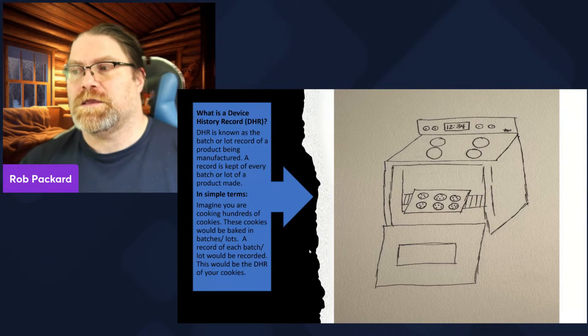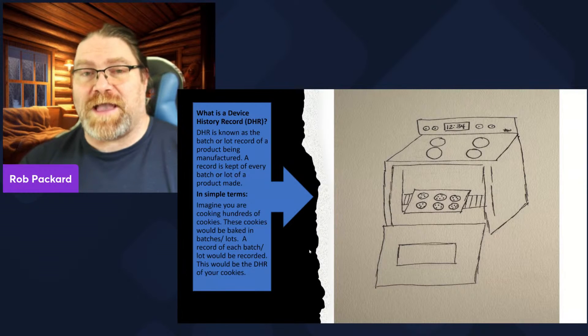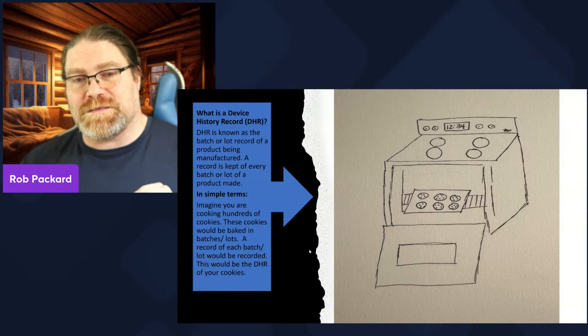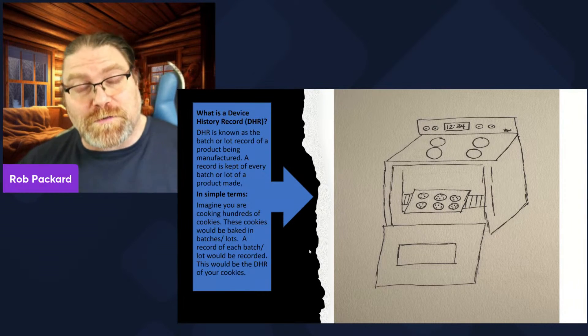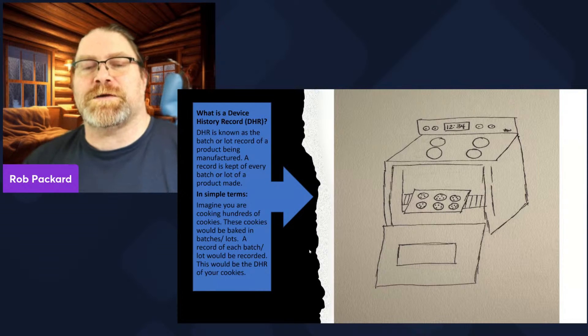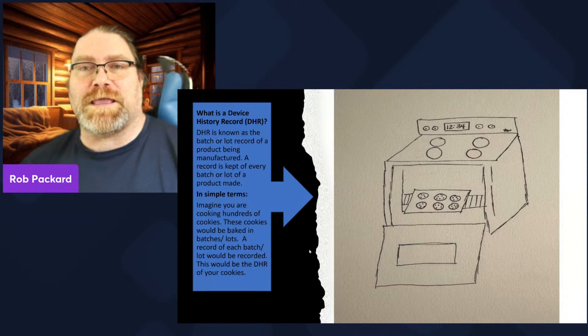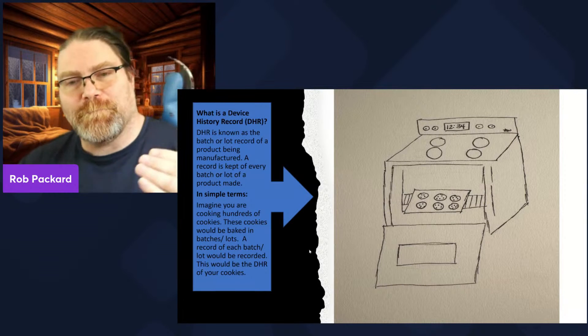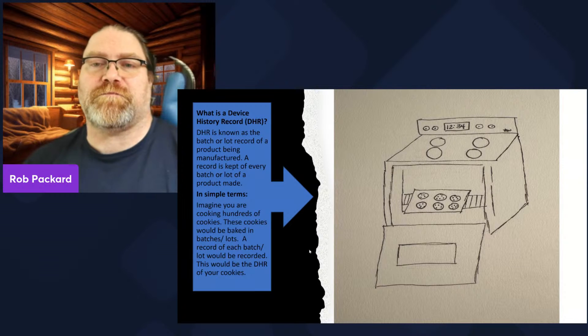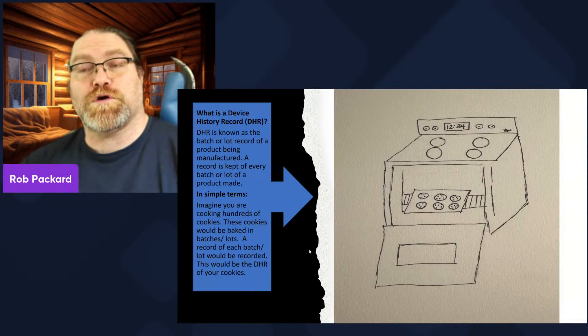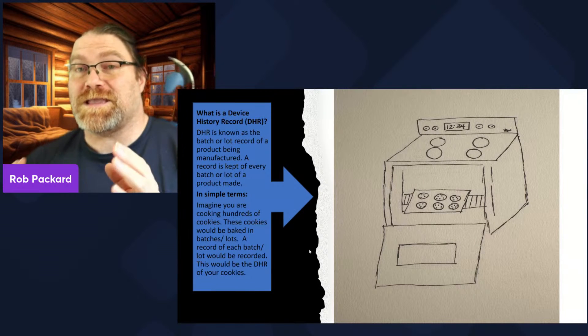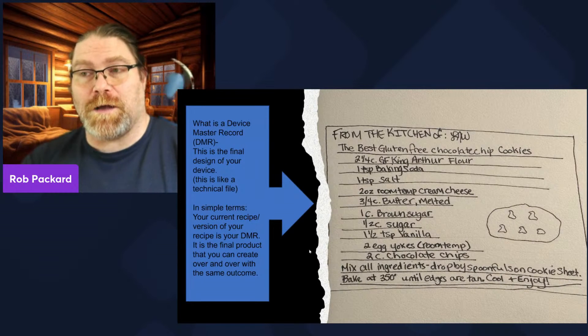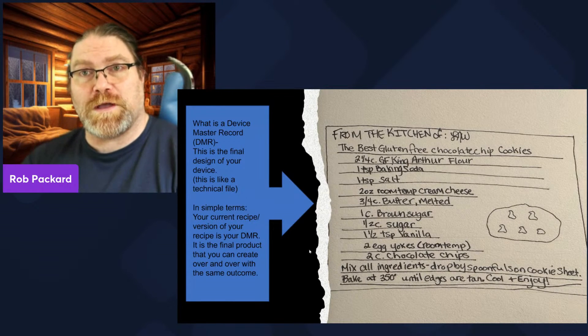But first I'd find out how they did it to make sure they weren't taking a shortcut that was unsafe or made bad product — make sure they're not cutting corners. You can make a batch of cookies faster if you throw the whole egg in shell and all, but cracking the egg carefully and leaving out the shells is preferred. That's not the way we want people making medical devices. So make sure the faster way is safe and makes good product before telling everybody to do it the new way. And that's a change to your DMR.